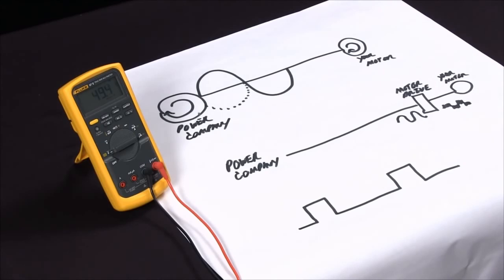And so this is how you can use the Fluke 87 to measure frequency and duty cycle and actually measure frequency much more accurately on motor drive systems.